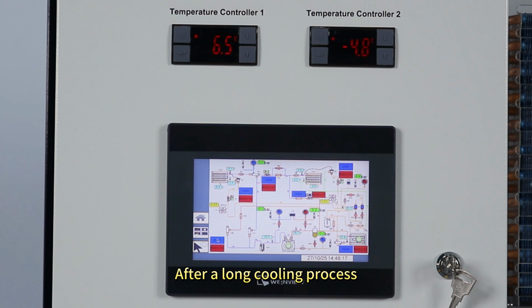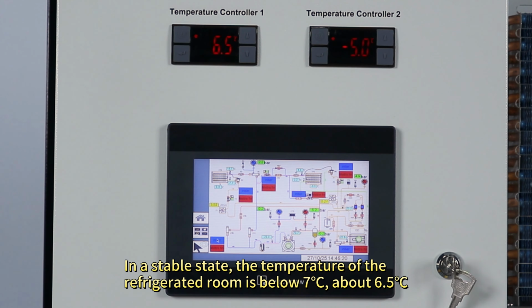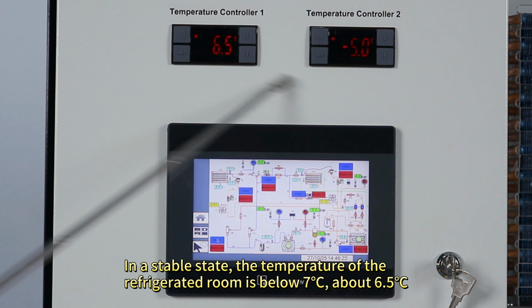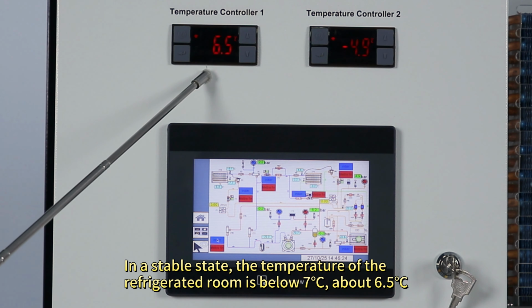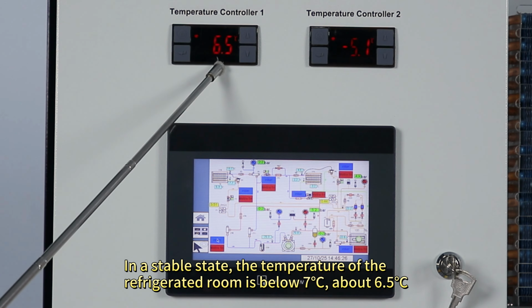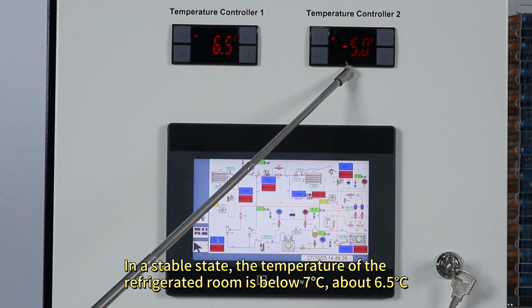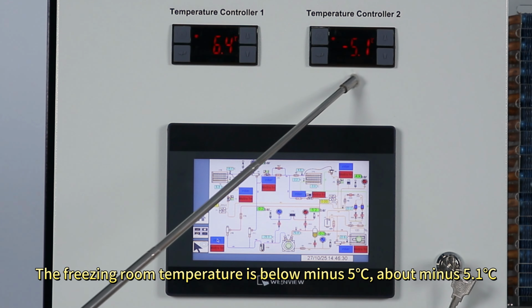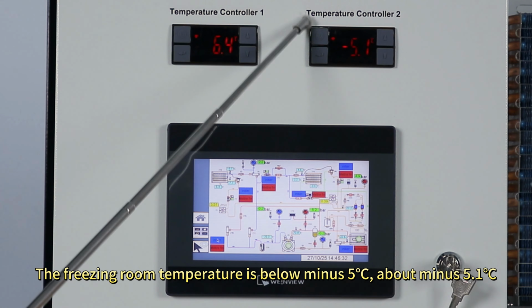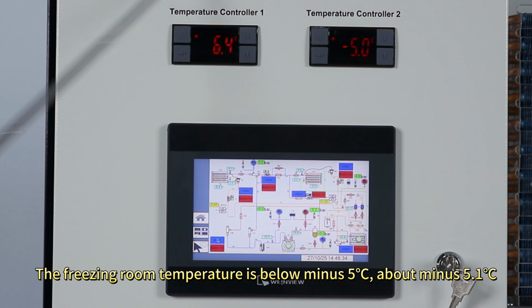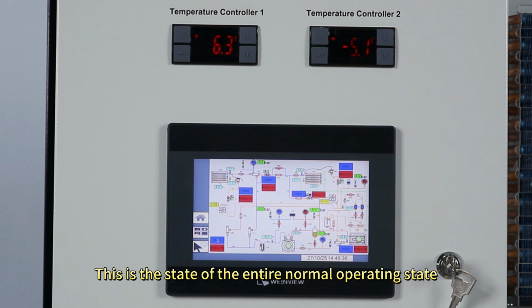After a long cooling process, in a stable state, the temperature of the refrigerated room is below 7 degrees centigrade, about 6.5 degrees centigrade. The freezing room temperature is below minus 5 degrees centigrade, about minus 5.1 degrees centigrade. This is the state of the entire normal operating state.